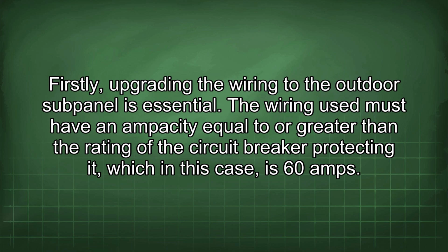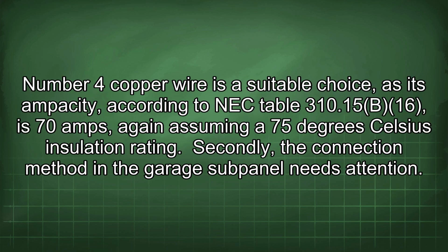Firstly, upgrading the wiring to the outdoor subpanel is essential. The wiring used must have an ampacity equal to or greater than the rating of the circuit breaker protecting it, which in this case is 60 amps. Number 4 copper wire is a suitable choice, as its ampacity, according to NEC table 310.15(B)(16), is 70 amps, again assuming a 75 degrees Celsius insulation rating.